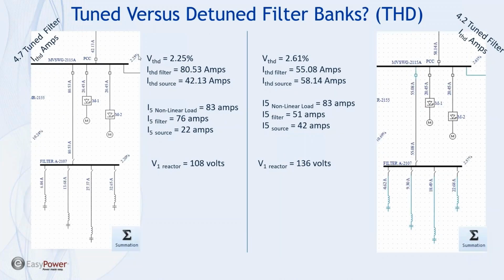I also want to note the bus voltage distortion. Obviously, the tuned filter is going to do a slightly better job in reducing the bus voltage distortion versus the system here on the right, which is detuned. It's at 2.61. Because the filter is slightly less effective, of course, we get a little bit more voltage distortion for a detuned system.